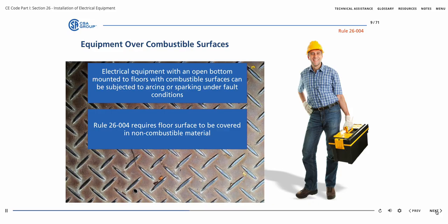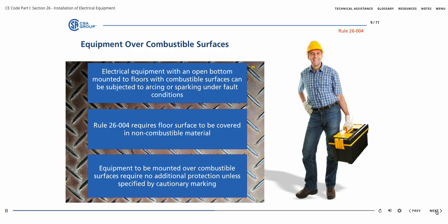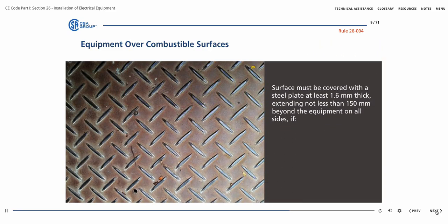The certification requirements for electrical equipment state that all equipment to be mounted directly over combustible surfaces do not require any additional protection, unless the equipment bears a cautionary marking clearly indicating that additional protection is necessary. The surface must be covered with a steel plate at least 1.6 millimeters thick, extending not less than 150 millimeters beyond the equipment on all sides, if the equipment is marked to require such protection or the equipment is open at the bottom.